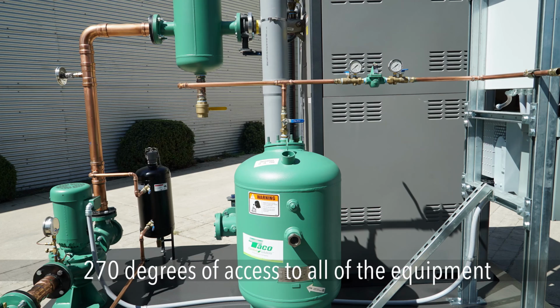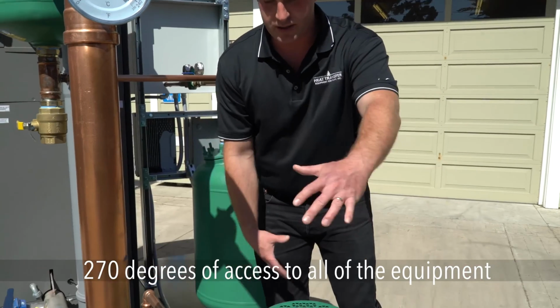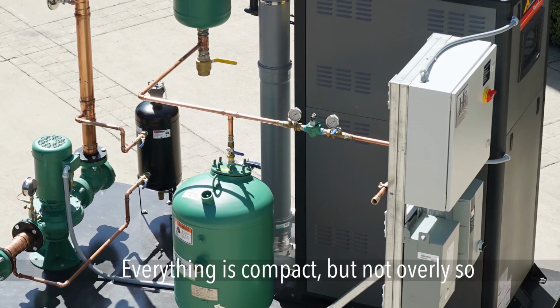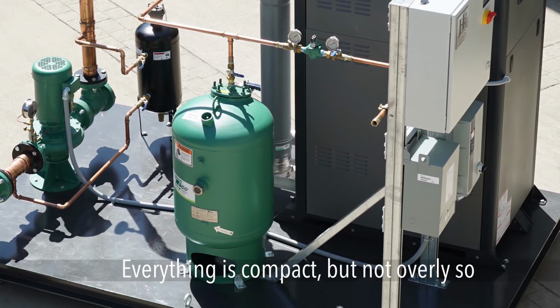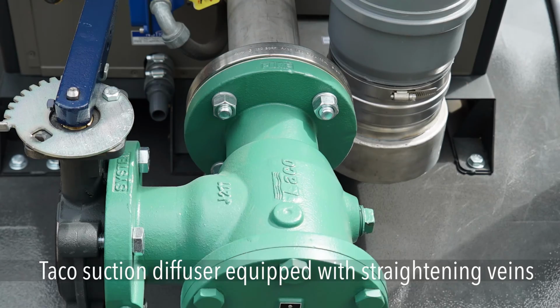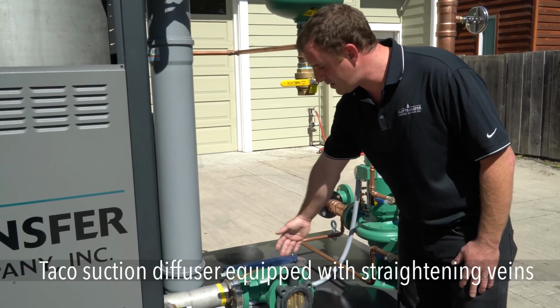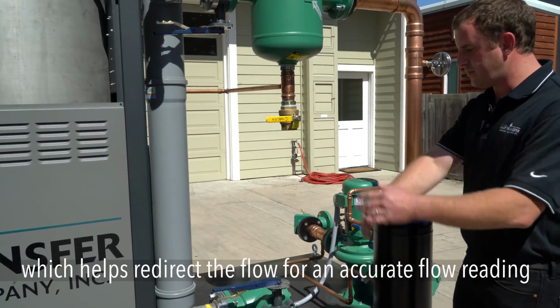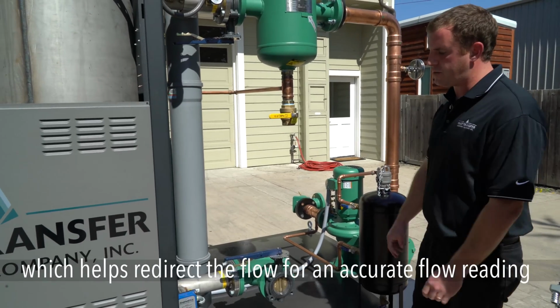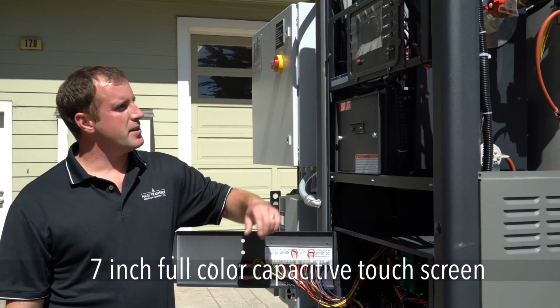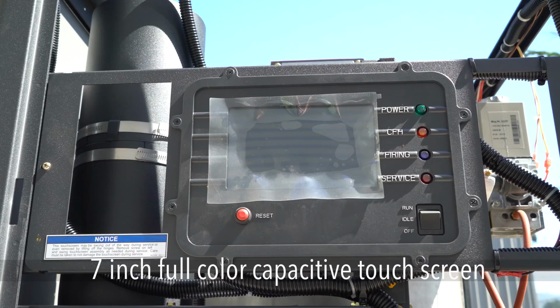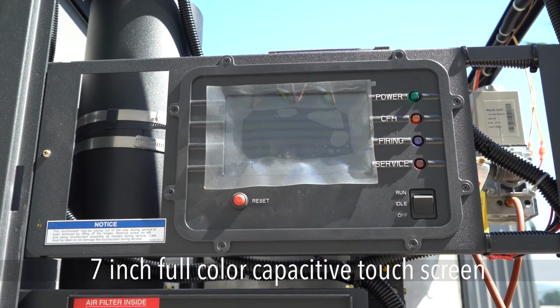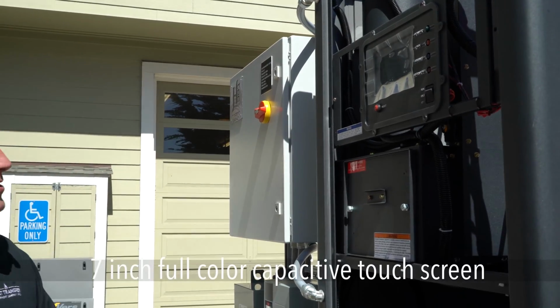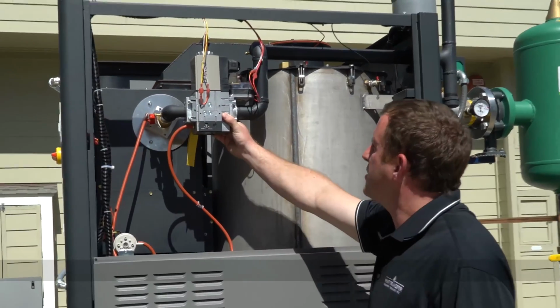Servicing the pump will never be a problem because there is 270 degrees of access. Everything is compact but not overly so. We've equipped a Taco suction diffuser which has straightening vanes in it, which helps redirect the flow, make sure that we get a good accurate flow reading all the time for the boiler. Raypak offers a 7-inch full-color capacitive touchscreen. It will actually respond to your touch if you have gloves on. We have a Dungs modulating gas valve.